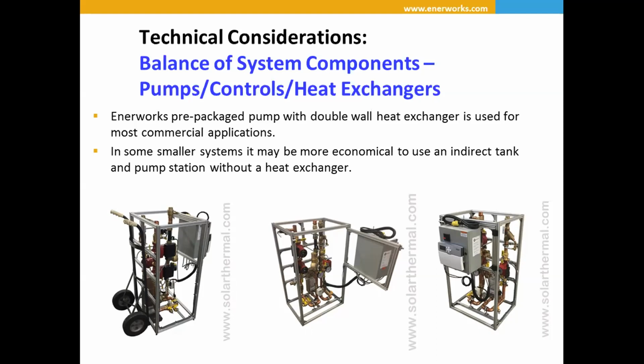So why that's important is because the system will sometimes stop and start during a cloudy day. You don't necessarily need to bypass that, but particularly as you go further north in California, you could have just above freezing temperatures in the loop, or even below freezing. You don't want the heat exchanger exposed to that. Even if you don't have freeze protection concerns, you don't really want to heat a tank up and then siphon the heat out. So having the bypass loop does two things there. It increases your overall system efficiency and adds an extra layer of protection. So this has your PRVs, check valves, and it has a digital pressure and a digital flow meter built into it that you can read from the control.